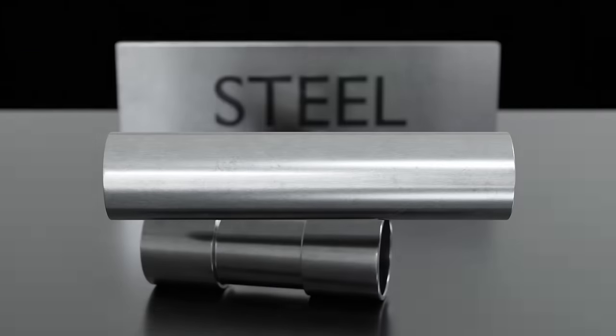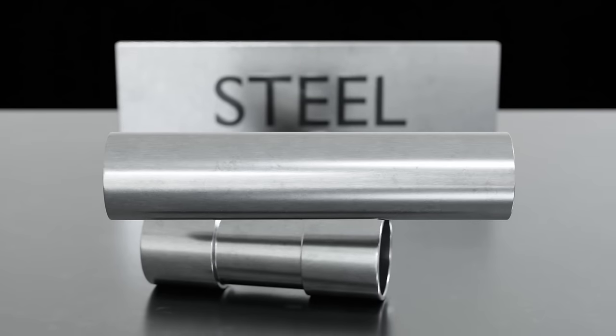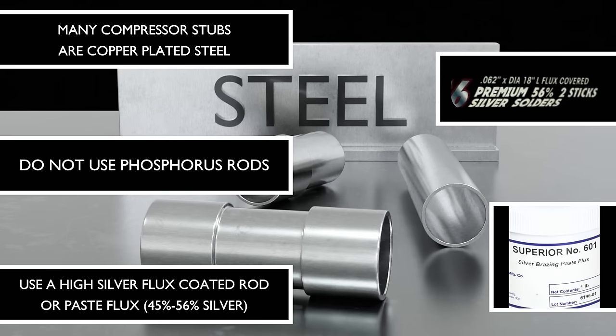Next, we have steel. You'll run into some valves that are made of steel. And you'll certainly run into steel on compressor stubs if the copper plating is burned through. And in some cases, the stubs may just be steel. When you're working with steel, do not use phosphorus-bearing rods. Any rod that says PHOS on the packaging, or has phosphorus in them, should not be used on steel. Use a high silver flux-coated rod or a high silver rod or wire with a separate paste flux, as shown here.